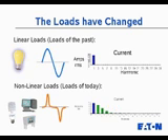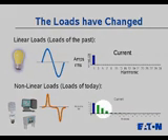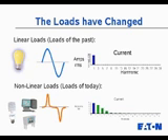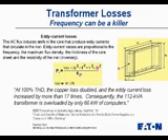If we size our electrical system to handle only the 60 Hz component, we're really in trouble. This has instigated a lot of the changes in today's types of systems where things are oversized or doubled — that effect comes from having to carry this additional amount of current. The third harmonic, for example, is probably an additional 50 to 75 percent of the fundamental, and remember these are RMS amps, so this is heating amperage. A lot of additional current is flowing in today's power systems. To understand how these higher-order frequencies — these harmonics — are interacting with our system, let's look at one of the types of losses that occurs inside a transformer, for example the eddy current loss.